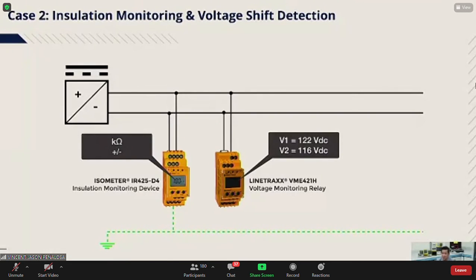Whether it's a symmetrical or asymmetrical fault. But the application that the customer wanted to find out was how much of that voltage shift was actually going to ground. So what we did is we just included a voltage monitoring relay. We didn't use the trip units. We didn't use the dry contact outputs to trip anything. We just used it to measure voltage of the DC circuit. And since it has a small footprint similar to the IMD, meaning the insulation monitoring device, it was a perfect fit for a small panel.